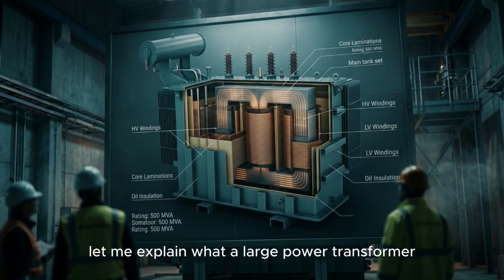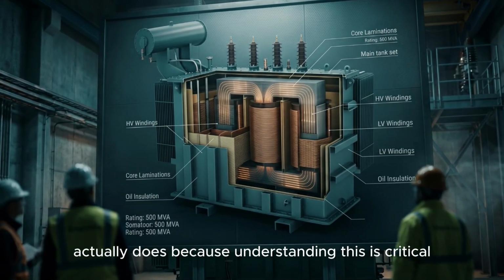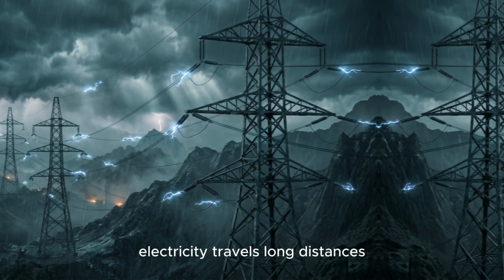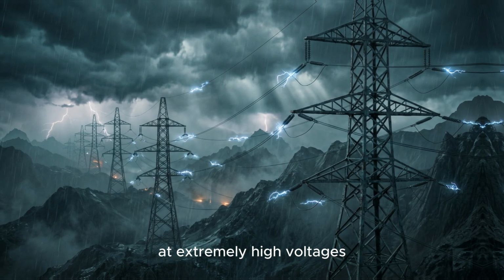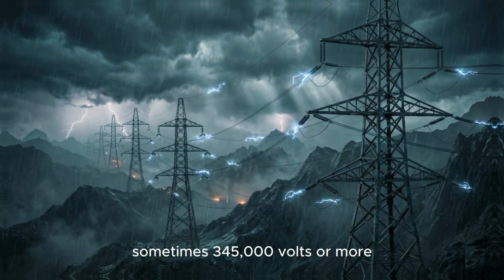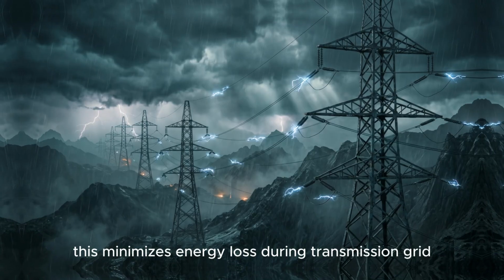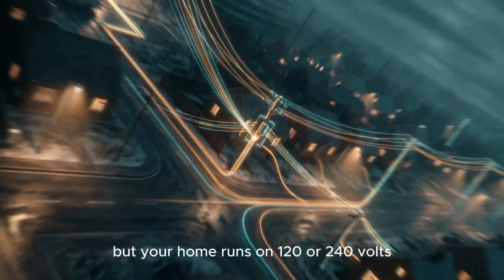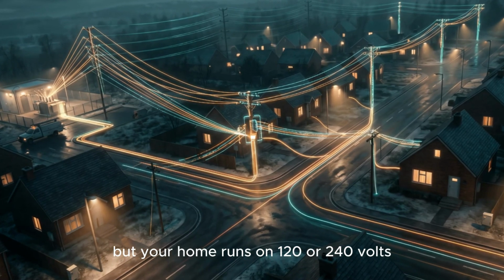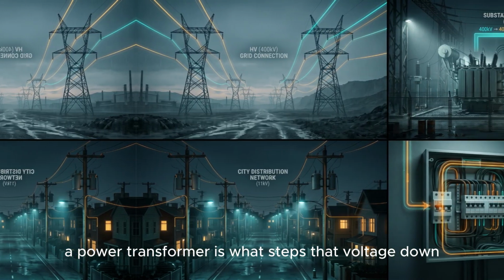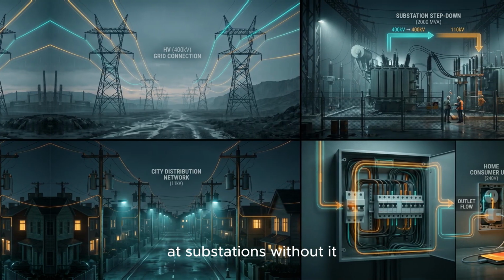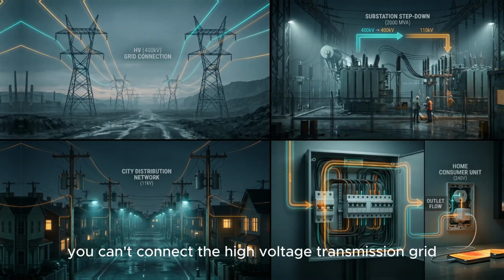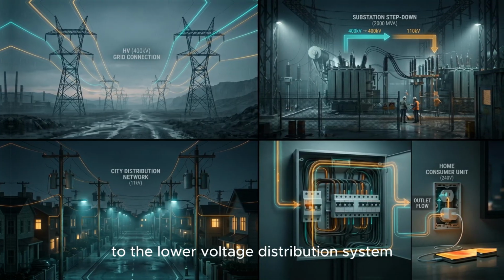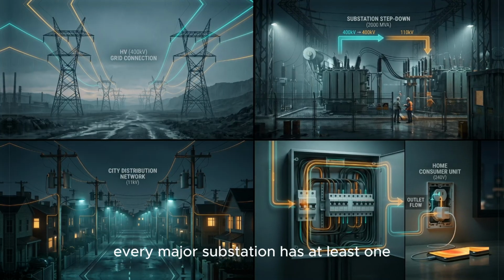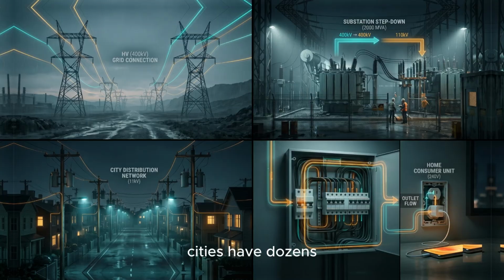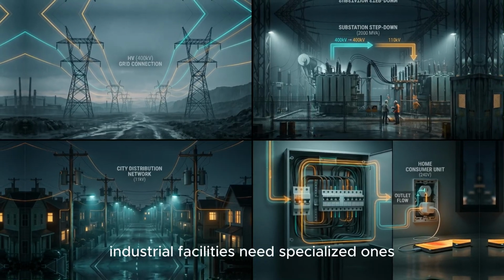Let me explain what a large power transformer actually does, because understanding this is critical. Electricity travels long distances at extremely high voltages, sometimes 345,000 volts or more. This minimizes energy loss during transmission. But your home runs on 120 or 240 volts. A power transformer is what steps that voltage down at substations. Without it, you can't connect the high voltage transmission grid to the lower voltage distribution system that feeds neighborhoods. Every major substation has at least one. Cities have dozens. Industrial facilities need specialized ones.